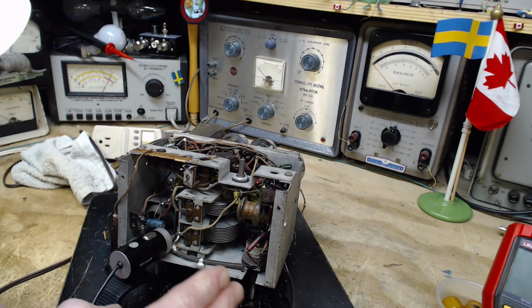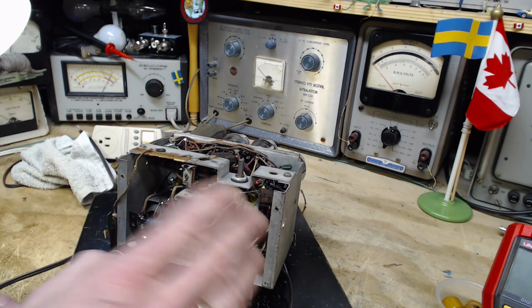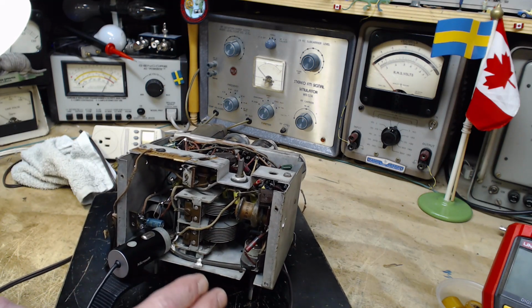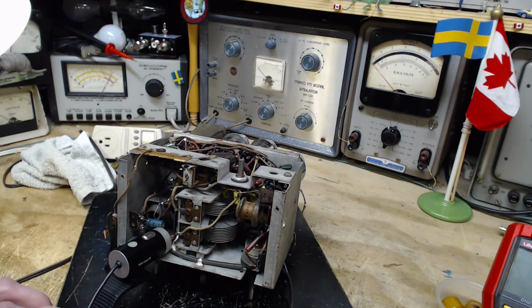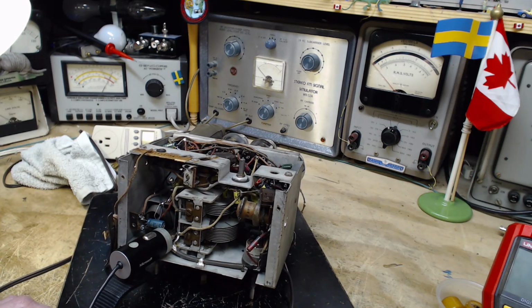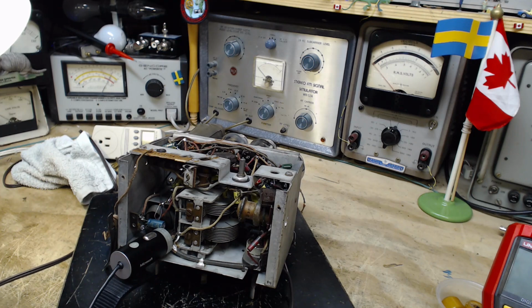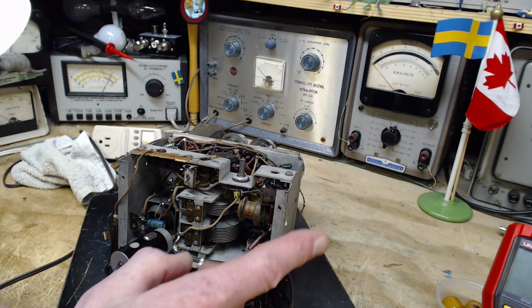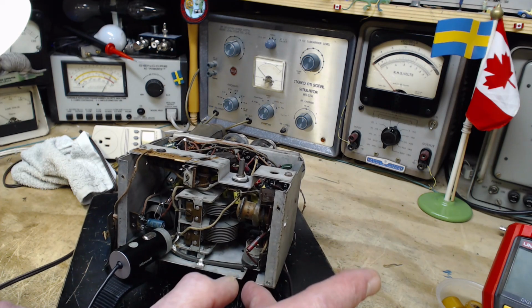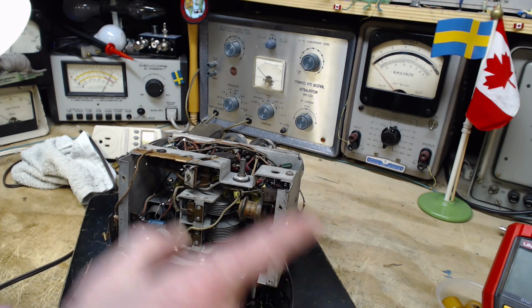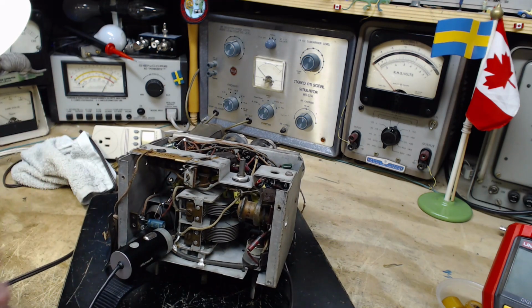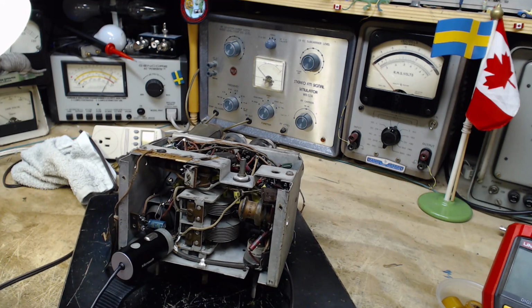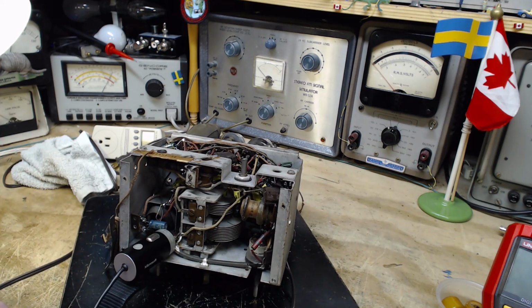If you did the opposite, if you weren't careful and just made the splices good enough to do the job they have to do, then in times of extraordinary stress - cable failures, short circuits, high load, switching errors, whatever - you could damage the cable at every joint very quickly. Every splice would get ruined from overheating, and you could do like $1 million worth of damage in a couple hours.